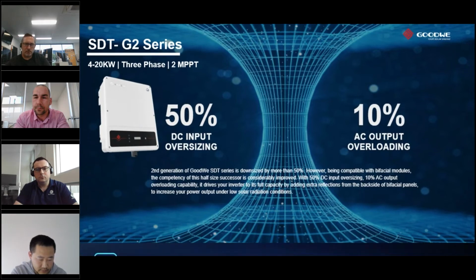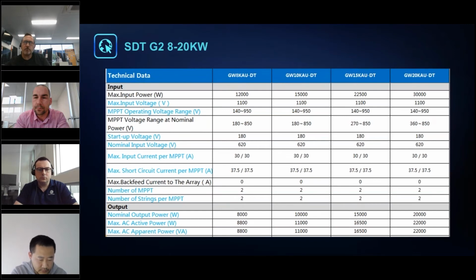And you can see here on this slide, I'll highlight some of the differences between the G1 and the G2. Probably the most redeeming feature is the inbuilt DC isolator. We had it on the 5 and 6 because it was a G2, but everything from 8 to 20 kilowatts previously didn't have an inbuilt DC isolator. It now does. Another difference is the maximum input voltage, which is now 1100 volts. As I said before, that allows you to add an extra couple of panels in each of your strings. And lastly, the number of inputs effectively going from 3 to 4. On the previous generation, there was a slight limitation if you tried to oversize on the 15 kilowatt inverter in particular, but certainly no limitation there moving forward.